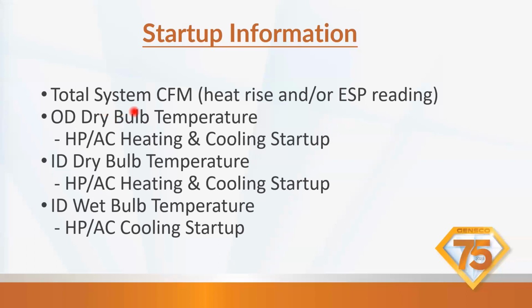Startup information, we want total system CFM, heat rise, and external static pressure reading. We want your outdoor dry bulb temperature. If we do have issues and you guys call in, these are all factors that we're going to ask for a detailed diagnostic. To assist you with diagnostic, we have to know this data.